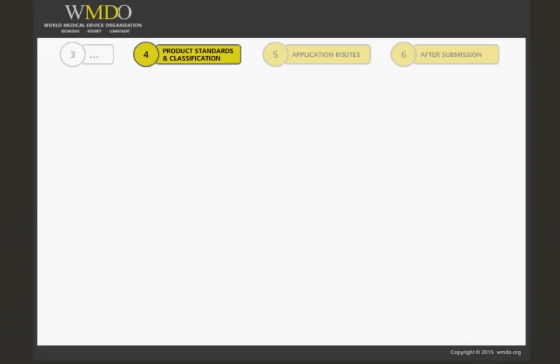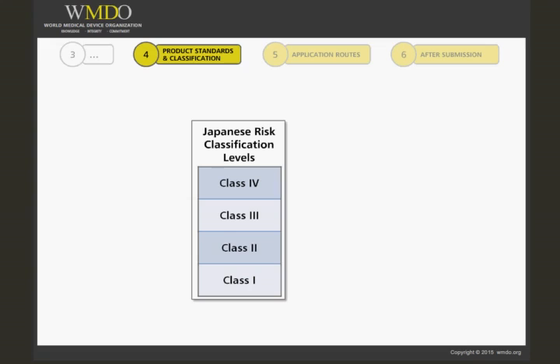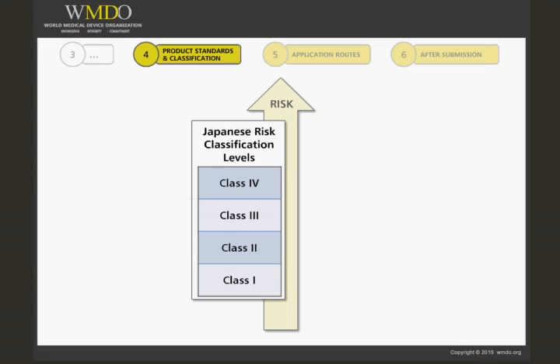For the PMDA, medical devices are reviewed based on risk classification. In Japan, there are four risk classification levels, class 1 to 4, with class 1 being the least risky and class 4 being the most. This is the first step that will determine your submission strategy: classifying your device.